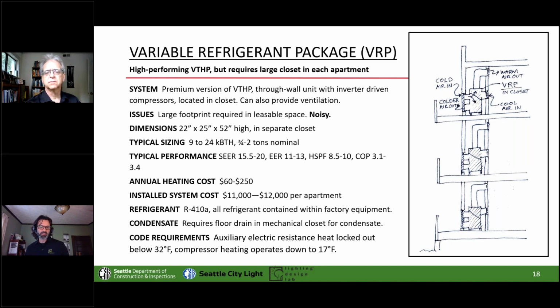But the compressor does a slow ramp up, as does the fan. So it's a little less of the rumble to life and rumble back off. At least it comes up over 20 seconds, right? Which is a little less jarring. And the fan and compressor are noticeably quieter if you've been in two buildings with the same thing. We're kind of getting used to the fact that a 700 square foot apartment is considered spacious now in Seattle, but a lot of the rest of the country still has much larger apartments and garden style apartments, and maybe there's room for such a thing there.